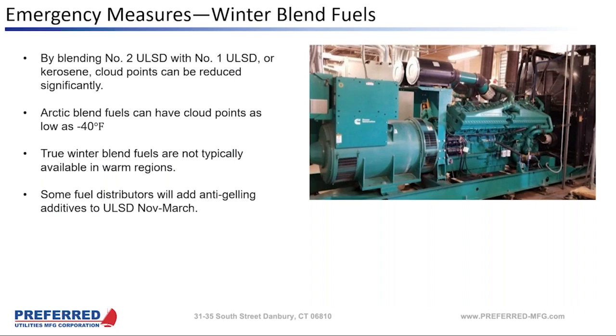It is. I would say though, for this to be a whole system approach, if you have a supplier that's adding anti-gelling November through March, keep in mind, if we're talking a mission critical or life safety facility, what is your delivery schedule, right? Are you getting deliveries in July, but you want your system obviously to run in January? So it's just going to take a lot more coordination with your fuel supplier. And that's one thing that we really can't control at the design phase. But if it's a facility, you really have to have that conversation with your fuel supplier to say, hey, I may be getting a delivery in August, but these are the considerations that I need to take year round. So it's just an extra layer of coordination.